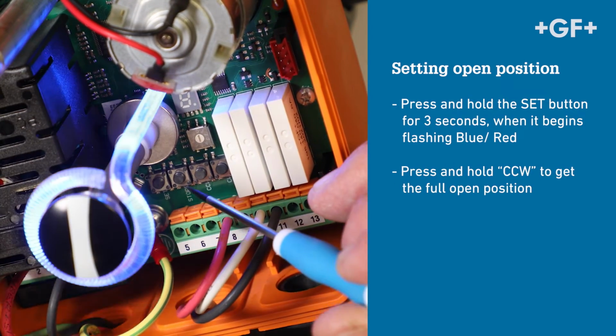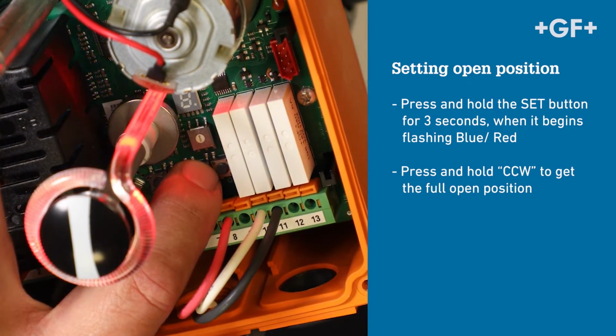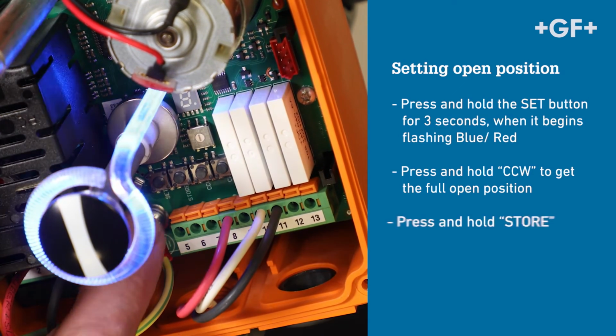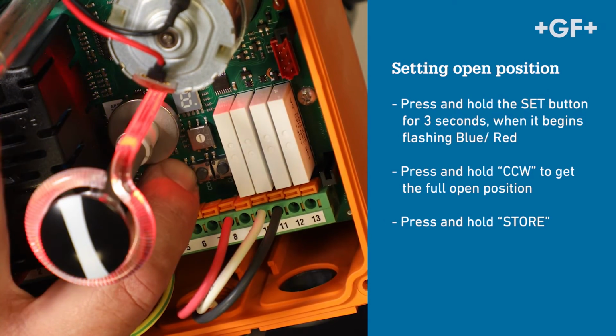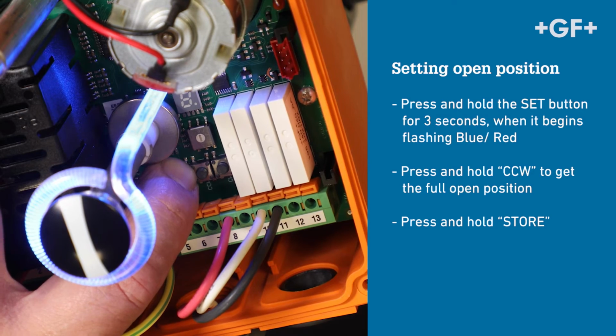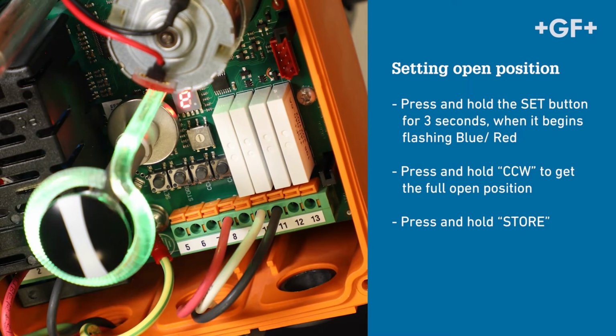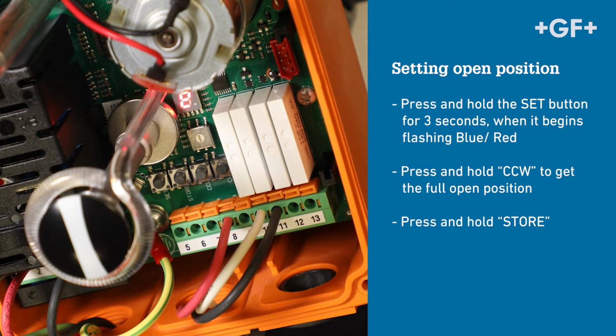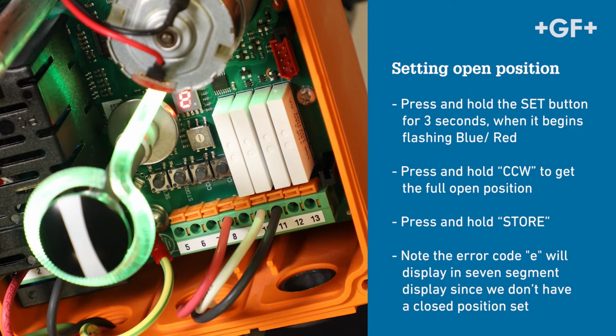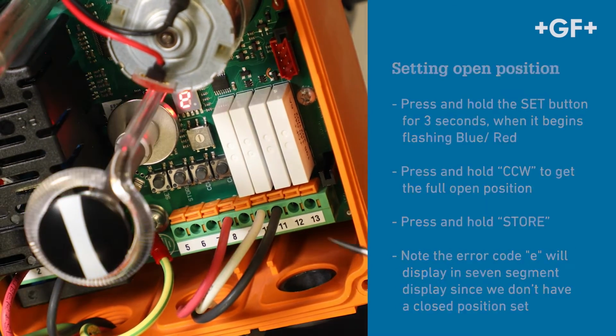Using the CCW button, rotate the valve to the full open position. Then, press and hold Store. The actuator will click, acknowledging the setting. The open position has been programmed. We still show an error because we don't have a closed position set, so let's do that now.